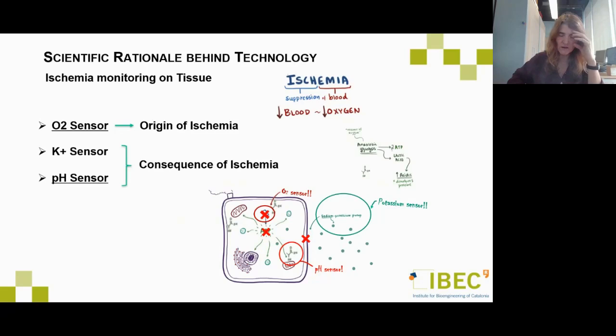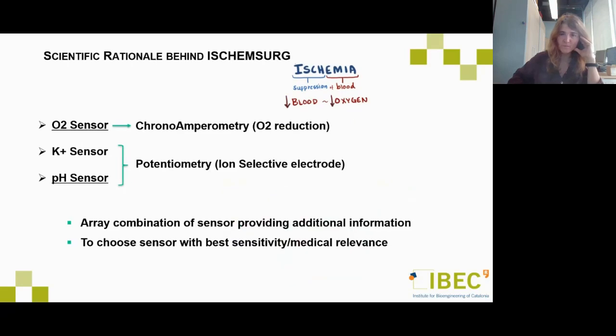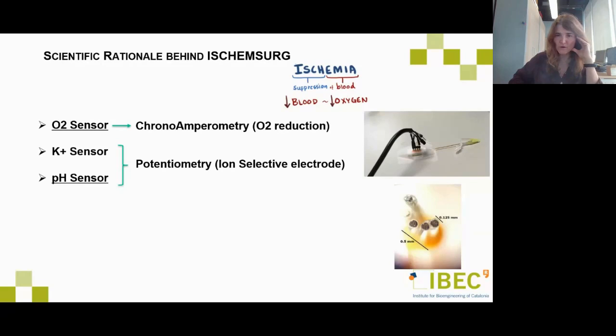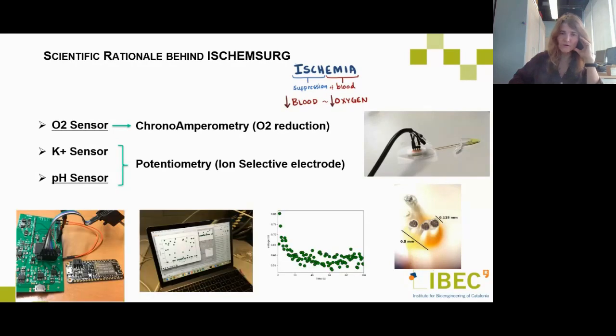And also the lack of oxygen makes the cell generate anaerobic respiration, producing lactic acid and then decreasing the pH in the tissue. So we are also able to detect it with a pH sensor. So basically, we are trying to combine two different analytes in order to have more information, oxygen and pH, with this micrometric wire of electrodes in an array format with electronics incorporated into the system.